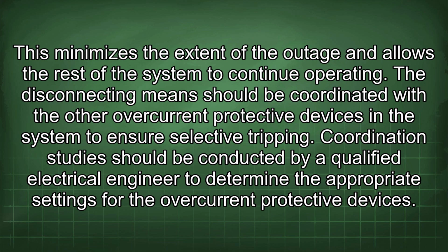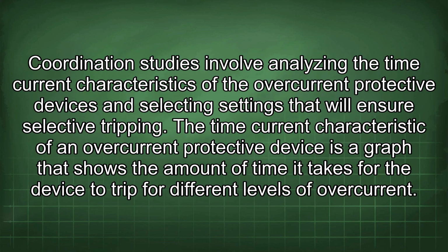Coordination studies should be conducted by a qualified electrical engineer to determine the appropriate settings for the overcurrent protective devices. Coordination studies involve analyzing the time current characteristics of the overcurrent protective devices and selecting settings that will ensure selective tripping. The time current characteristic of an overcurrent protective device is a graph that shows the amount of time it takes for the device to trip for different levels of overcurrent.